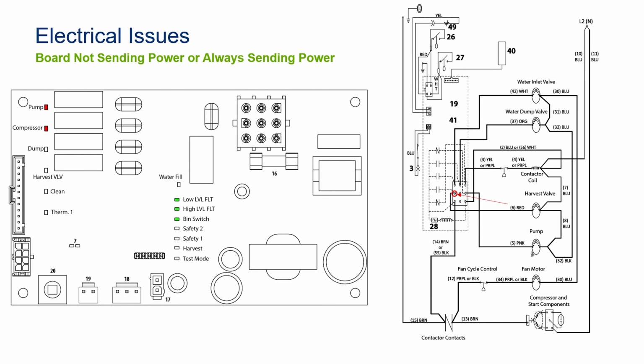What about board issues? So we've got a bit here. You see a control board. This is a machine that's in freeze. It has not consumed any of the water, so both floats are still satisfied. The damper is up, so the bin switch light is lit. The compressor and the pump relay are on.